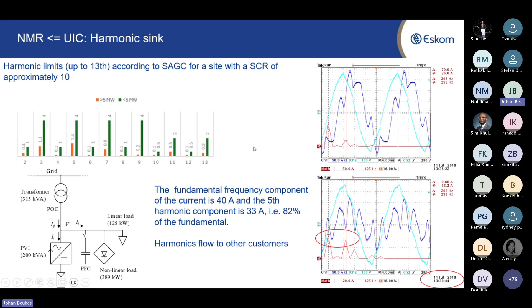Thanks. Yes, so I discussed SSO. From the Eskom side, what's important here is that we need to look at what's happening on the grid and at the non-fundamental frequency issues. We also looked at harmonics in another study, and we could show that grid-forming BESS improve harmonic performance. So what we need to do in future is develop specifications for BESS so that we use the capability of grid forming to compensate for things like SSO and harmonics, because grid-forming BESS acts as a voltage source, and that's what we want on the grid to support the grid. That's the message I wanted to convey. We have issues. Let's use grid-forming capability and use BESS to sort out these things.